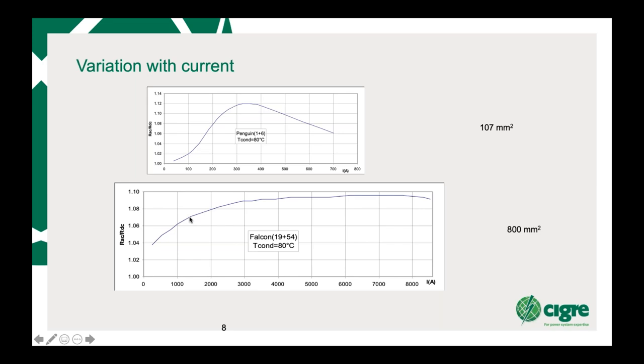And you can get those kind of currents if you're looking at emergency lines under emergency conditions. The double layer conductor, because of the cancelling effect, almost has no variation with current. And this is only with ACSR conductors, not with AAAC, ACCC or fiber cores. Now we've dealt with resistance.